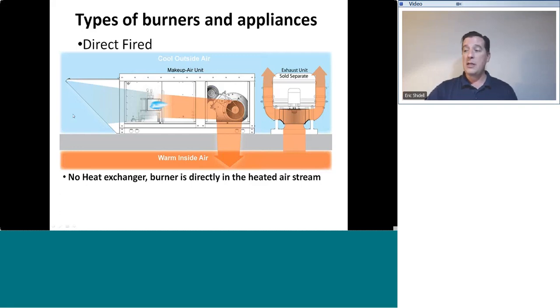In the dead of winter, say, for example, the outside air temperature is 0 degrees, now it will modulate the flame to a much higher level, a much stronger flame, to warm up that air 70 degrees as it passes through. So modulating burners are very common in direct fired appliances. And if you are in a market where you work on maybe a lot of direct fired appliances, if you work in the restaurant and food service field, I strongly recommend you get some additional training and education in modulating burner controls as applied to direct fired appliances, because that's a whole other topic of discussion, much different than your standard boiler or furnace or water heater type of gas controls.